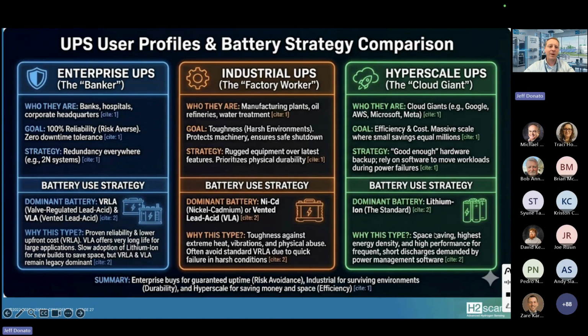These are places where you might find a three-phase UPS, and many local codes, standards, and directives require a hazardous mitigation program, because these are typically occupied buildings with hazardous materials that can generate hydrogen. So you have to have a plan to deal with that. We call that the hazardous mitigation program, and it's stated in both international IEC standards and a lot of local directives.